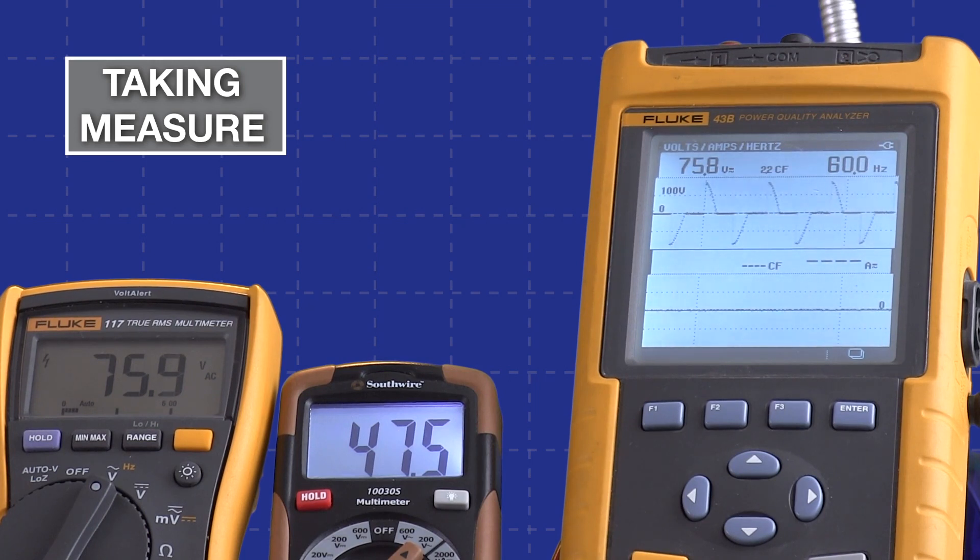The answer is pretty simple: the two Fluke meters are both true RMS meters, and they simply sample more of the sine wave more often and will give an accurate measurement even when you have altered sine waves. The Southwire meter is what's called an averaging meter, and it does not sample the sine wave in the same way and it will not give you an accurate measurement when you're dealing with any kind of an altered sine wave. There are lots of things in the electrical world that do alter the sine wave, so if you're working with AC circuits which may have some kind of a poor or manipulated sine wave, you need a true RMS meter to get both current and voltage measurements accurately.